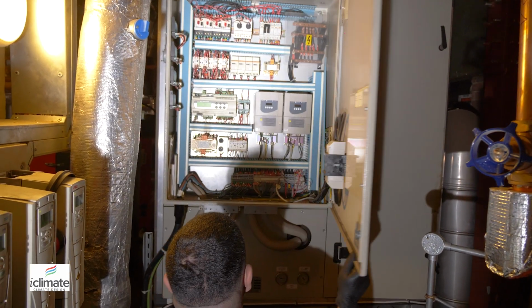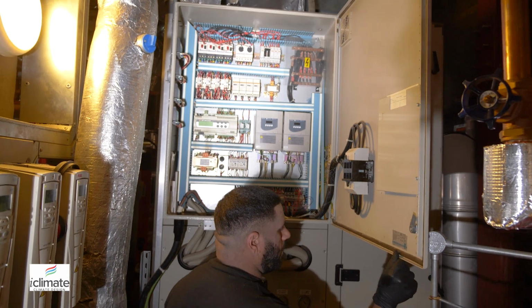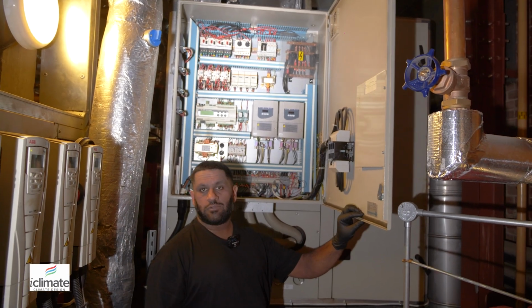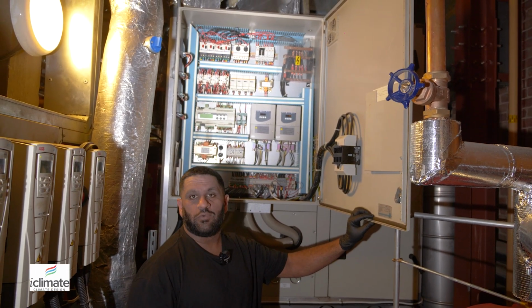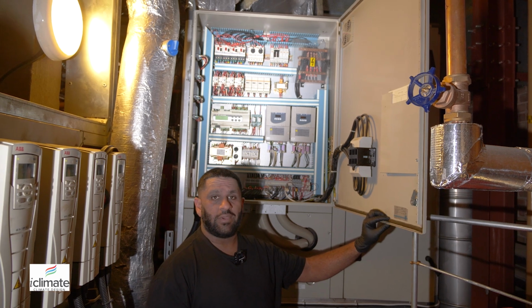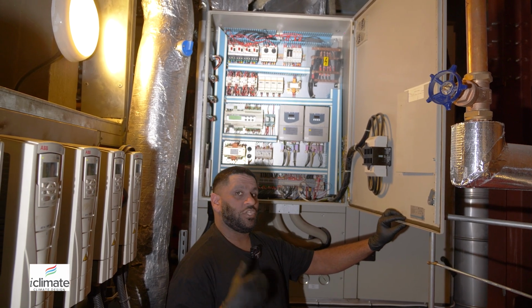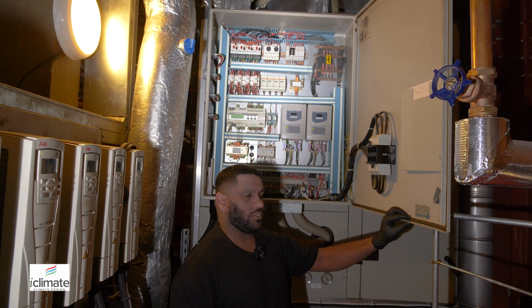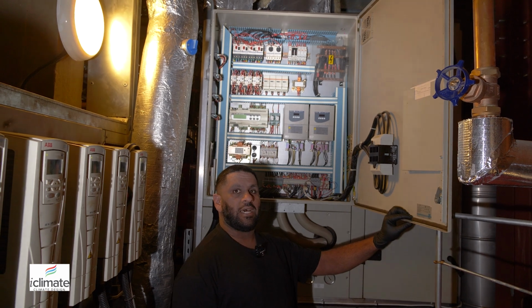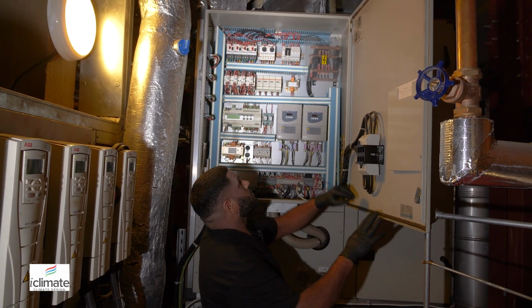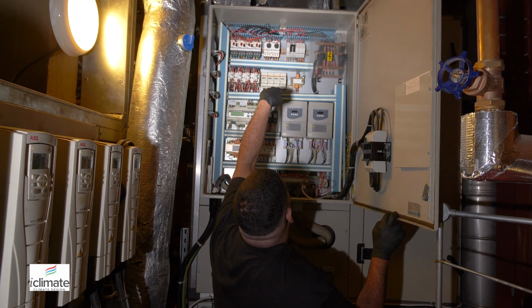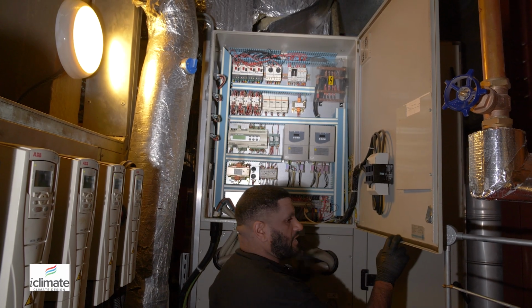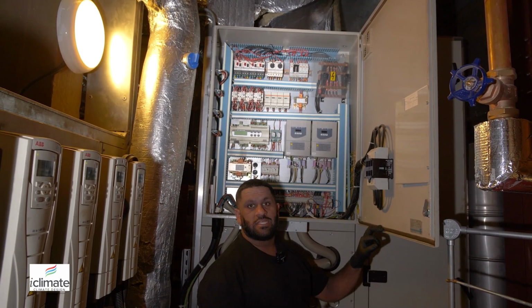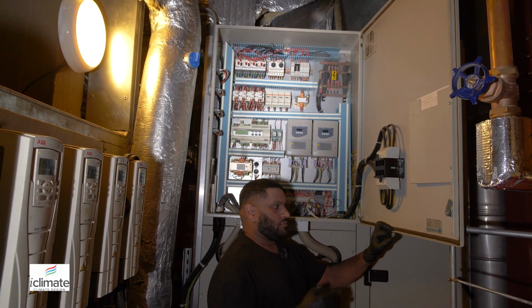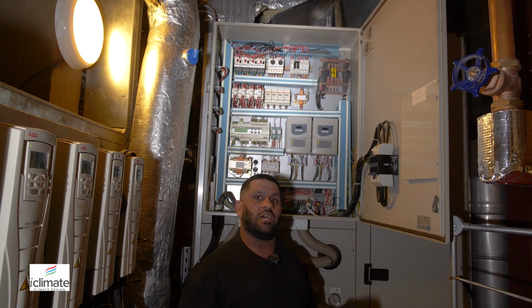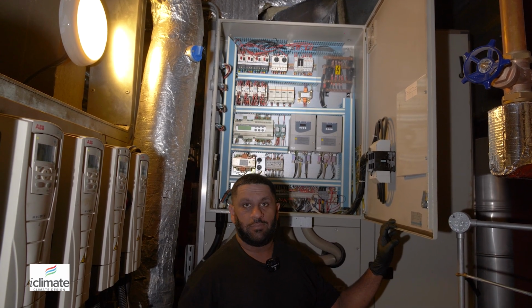This chiller is sitting inside the plant room like I mentioned earlier, because permission must not have been allowed when the fit out of this commercial building was carried out about 20 years ago to place a chiller outside. So in this scenario, the chiller gets placed inside and it's a ducted version. There's lots of ductwork bringing fresh air into the chiller, across the condenser, and then from the condenser to outside, okay? So plant rooms that have ducted chillers are essentially heavily ventilated plant rooms, right?